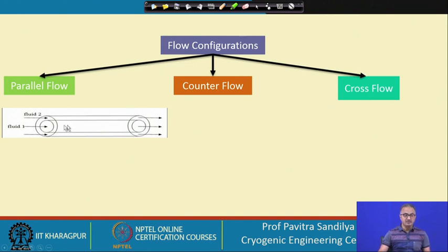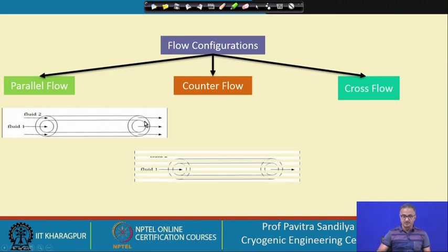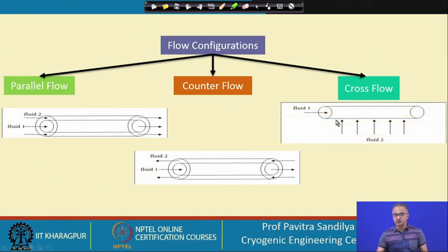In parallel flow, two fluids — fluid one and fluid two — flow in a set of concentric pipes, where the inner pipe is concentrically placed within an outer pipe. One fluid flows inside the inner pipe and another in the annular region between the two pipes. If these two fluids flow in the same direction, we call it a parallel flow configuration. If they flow in opposite directions, we have counter current flow. In cross flow, one fluid flows through the pipe while another crosses perpendicularly.